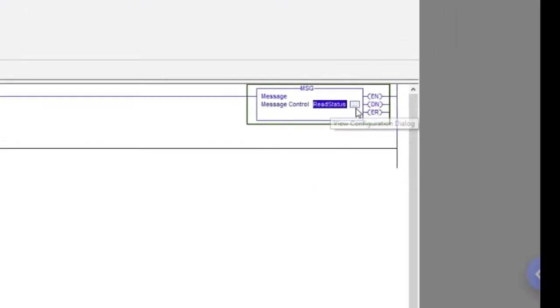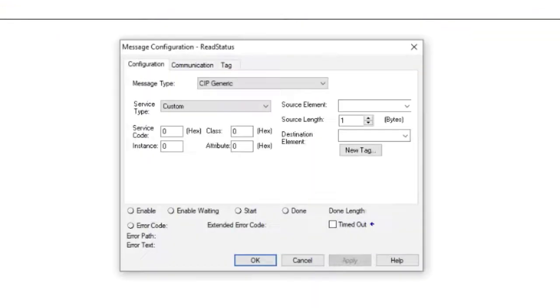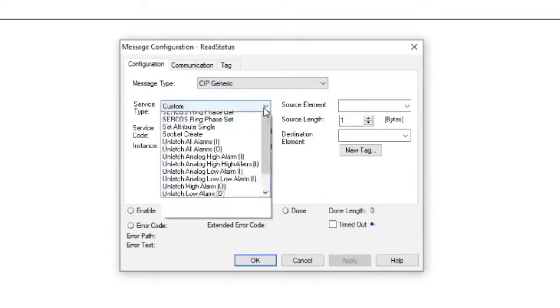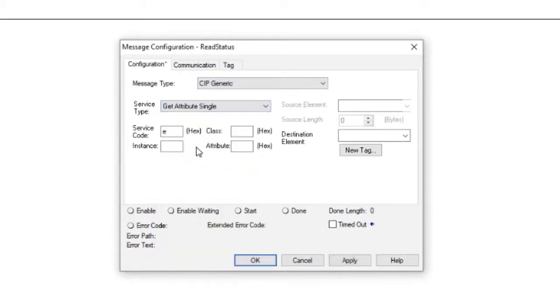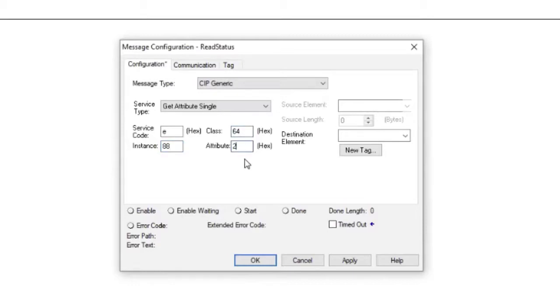Now that the message has a controller tag created, we can configure the instruction. The message type is CIP Generic. The service type is Get Attribute Single. The instance happens to be the starting Modbus address we want to read in the module, so we enter 88. The class is 64 and the attribute is 2, which is the number of registers we want to read beginning with 40088.